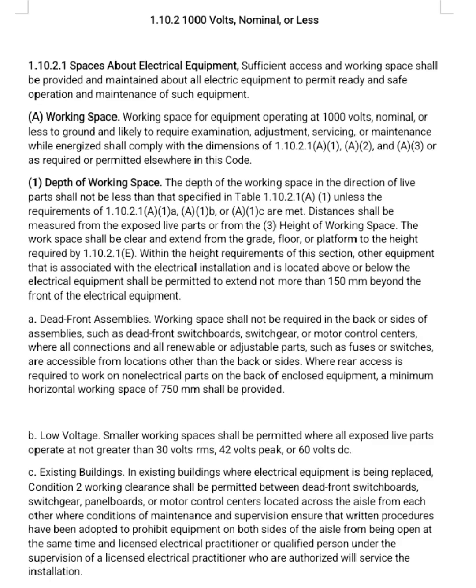A. Dead front assemblies. Working space shall not be required in the back or sides of assemblies, such as dead front switchboards, switchgear, or motor control centers, where all connections and all renewable or adjustable parts, such as fuses or switches, are accessible from locations other than the back or sides. Where rear access is required to work on non-electrical parts on the back of enclosed equipment, a minimum horizontal working space of 750 mm shall be provided.